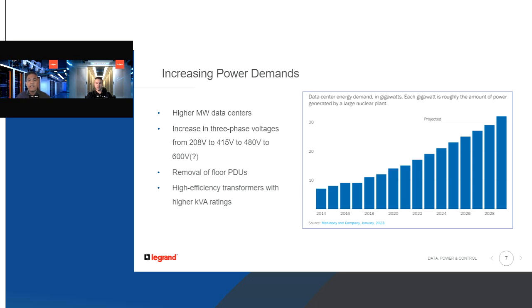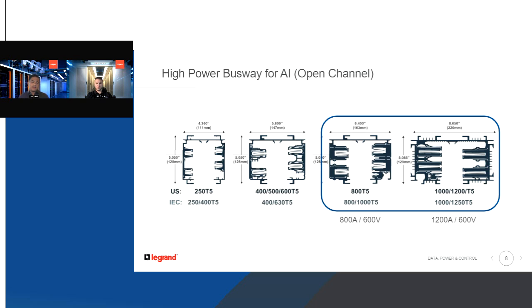On the busway level, the T5 family—10 years ago our high volume products were the 250 and 400 amp, pictured on the left. With AI rows and AI servers, we're seeing a huge shift to double the amount of power needed for these AI racks, so we're seeing more 800 amp and 1000 amp used in the data center space specifically to power AI racks. This is the higher end of the T5 family.